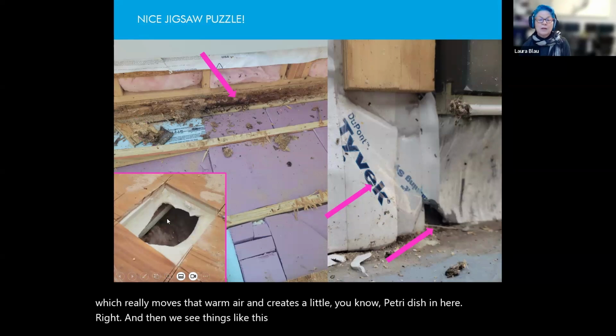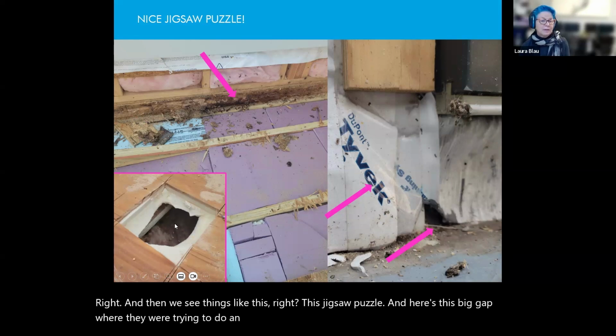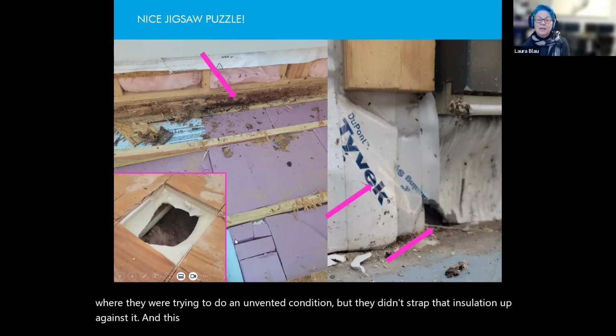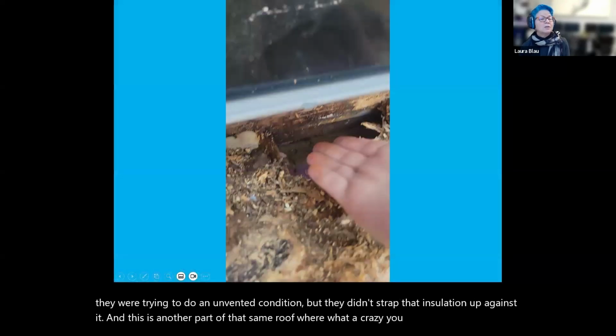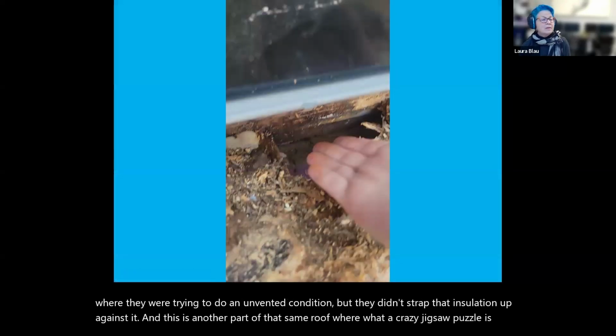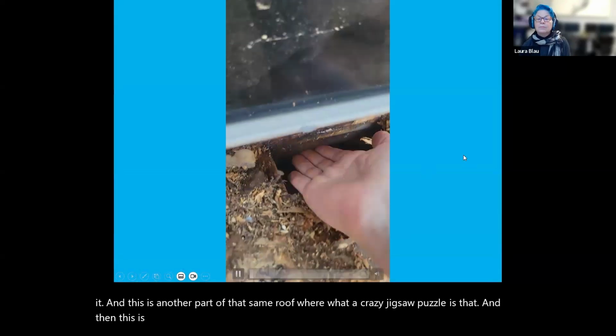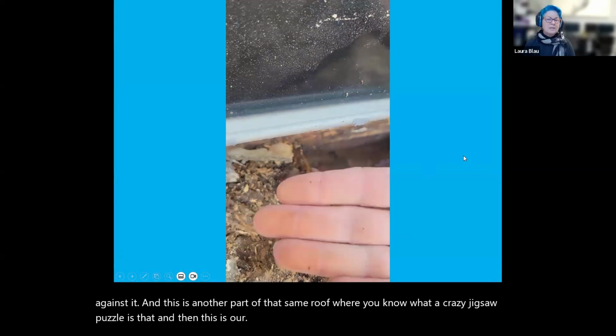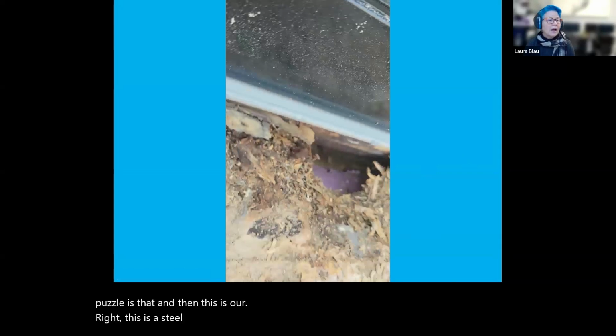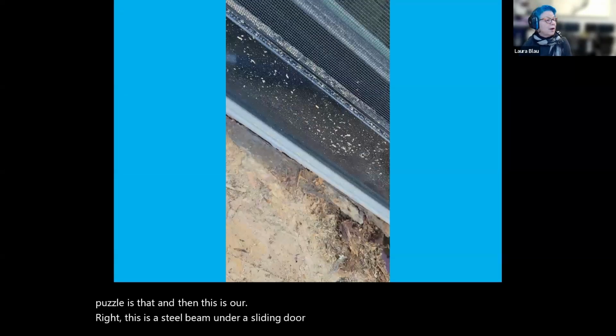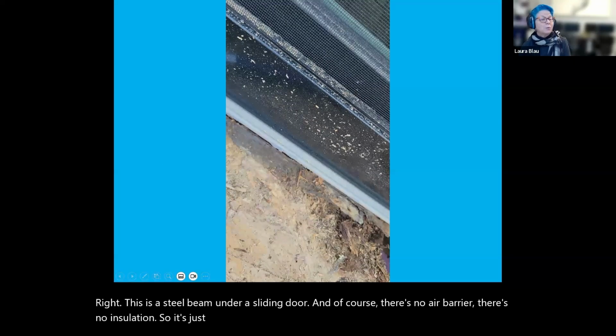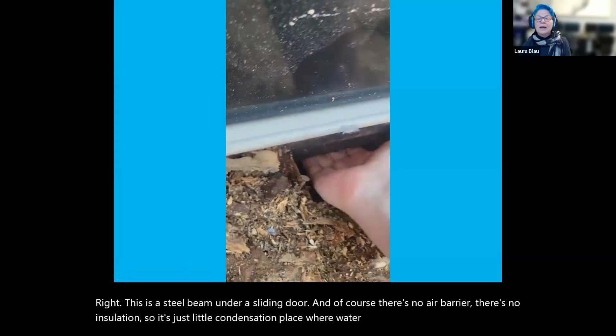And then we see things like this, right? This jigsaw puzzle, and here's this big gap where they were trying to do an unvented condition, but they didn't strap that insulation up against it. And this is another part of that same roof, what a crazy jigsaw puzzle that is. And then this is a steel beam under a sliding door. And of course, there's no air barrier, there's no insulation. So it's just a little condensation place where water gathers and it rots everything out.